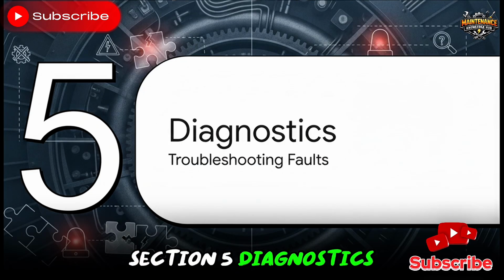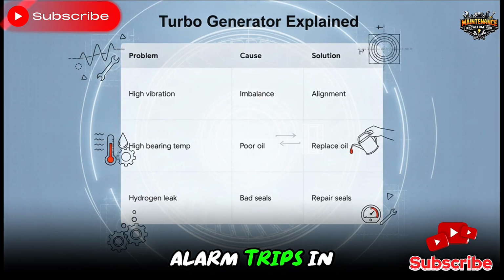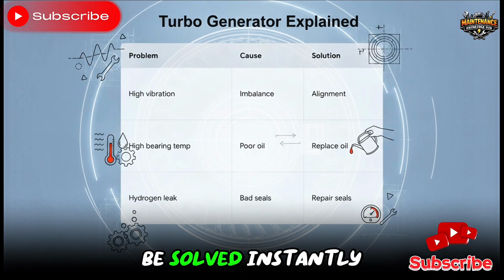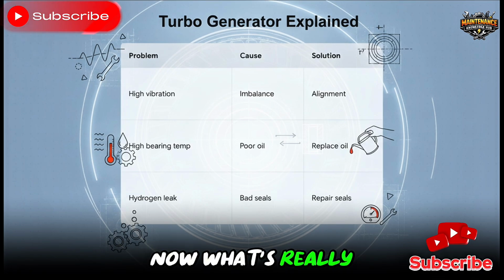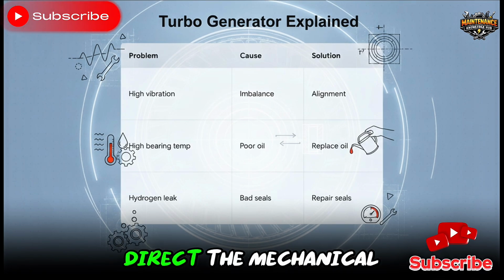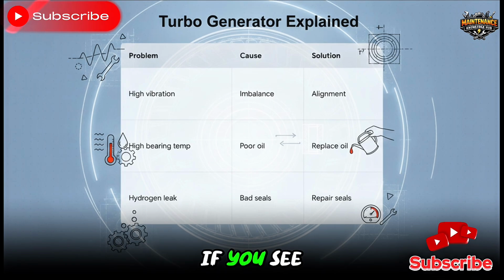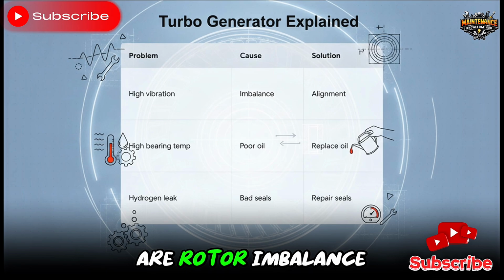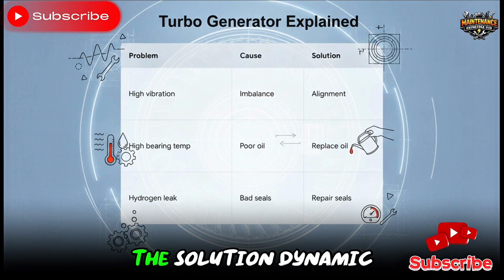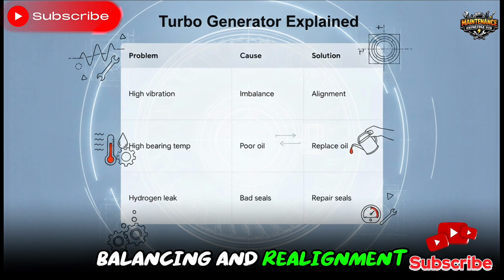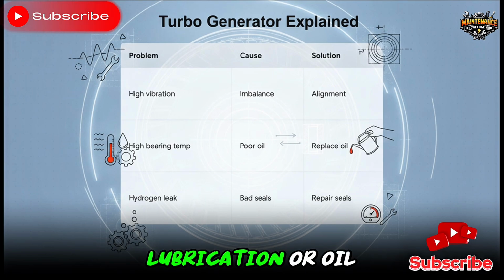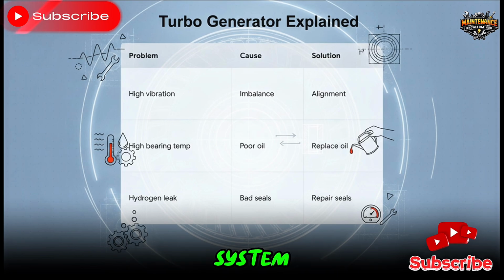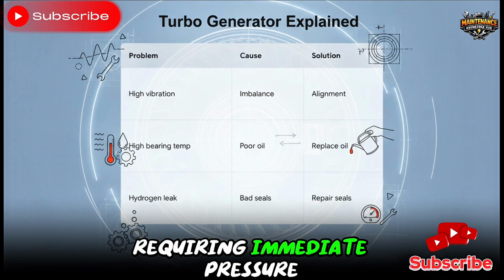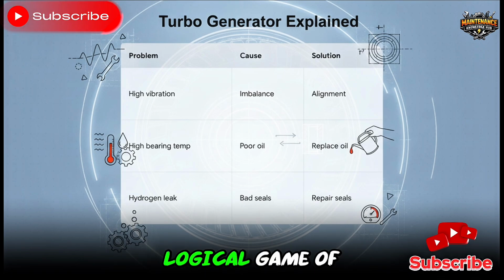Section 5. Diagnostics and Troubleshooting. So, when an alarm trips in the control room, engineers have to treat these faults as complex mechanical puzzles that need to be solved instantly to prevent downtime. Now, what's really interesting about this slide is how incredibly direct the mechanical cause and effect relationship is. If you see high vibration, your immediate suspects are rotor imbalance, shaft misalignment, or worn bearings. The solution? Dynamic balancing and realignment. High bearing temperatures, you look straight at poor lubrication or oil contamination, and you immediately check the oil system. Hydrogen leakage means your seal oil pressure is low or the seals are physically damaged, requiring immediate pressure restoration. It's a highly logical game of connect the dots.